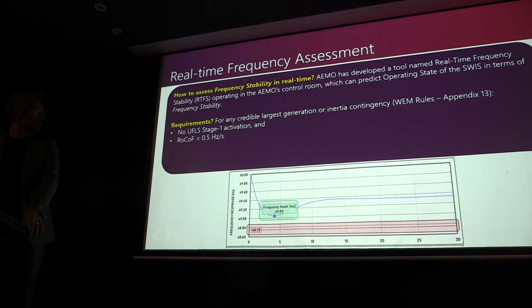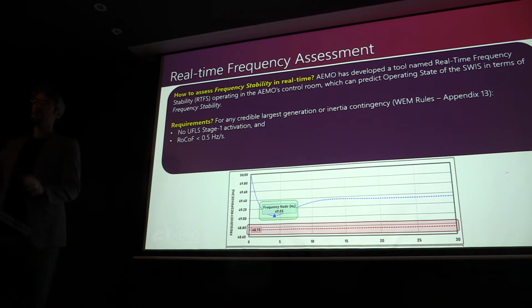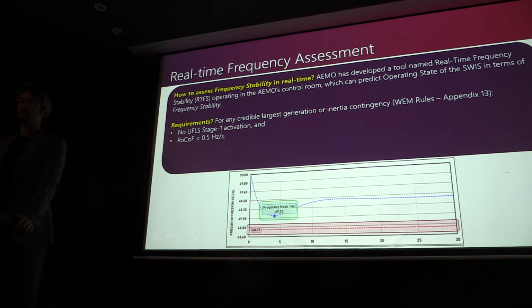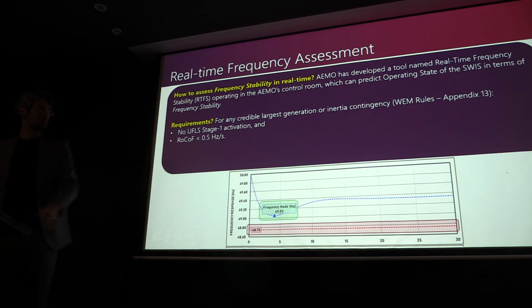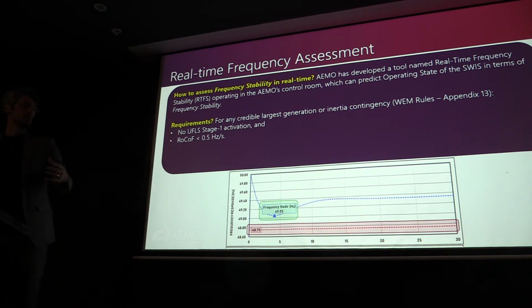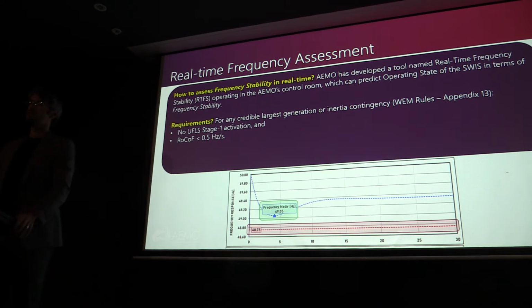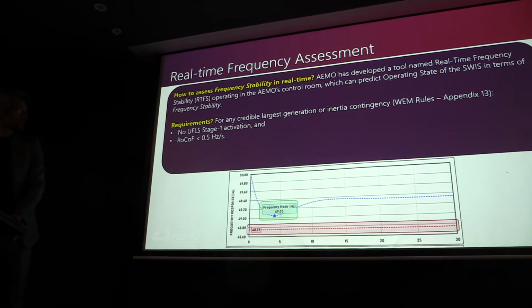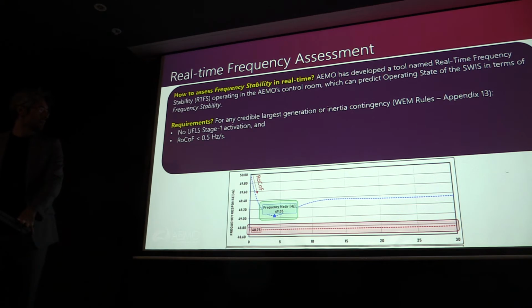Another requirement is RoCoF. RoCoF must not be above 0.5 hertz per second. That's another requirement which we need to achieve. Also, frequency should recover to a quasi steady state value. As you can see, a very nice recovery. After that, AGC will bring the frequency back to nominal value. That's the RoCoF, so we measure it and consider it to control.